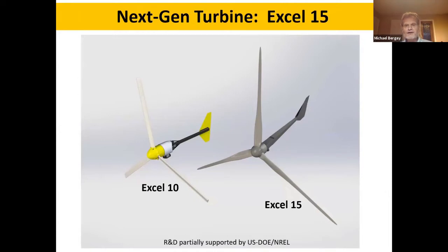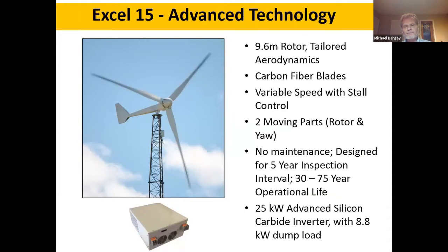The next generation Bergey turbines are very different from our old design. Here you can see our 10 kilowatt and our new 15 kilowatt turbines side by side in a rendering. The new turbine is stall regulated, does not furl, has a 9.6 meter rotor diameter, custom airfoils, and a custom blade planform. The blades are made from carbon fiber. It's a variable speed turbine up to the stall point, then we use a combination of inverter power and dump load to control rotor speed. The rotor has superior stall characteristics over other airfoils produced for small turbines.